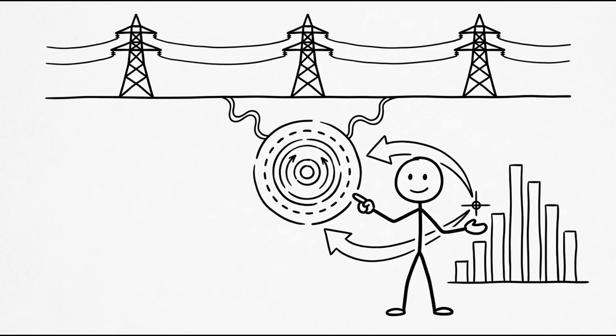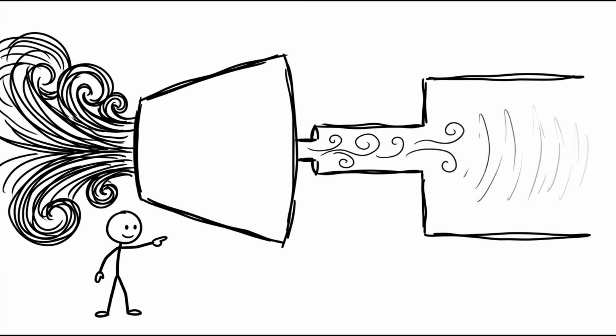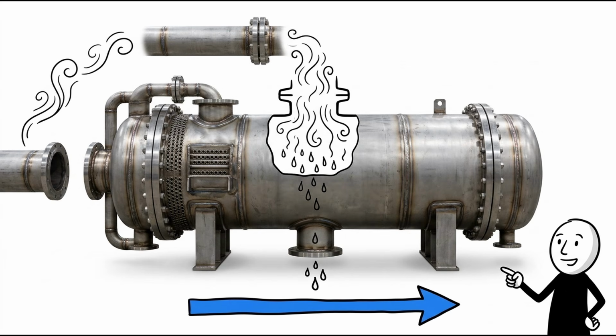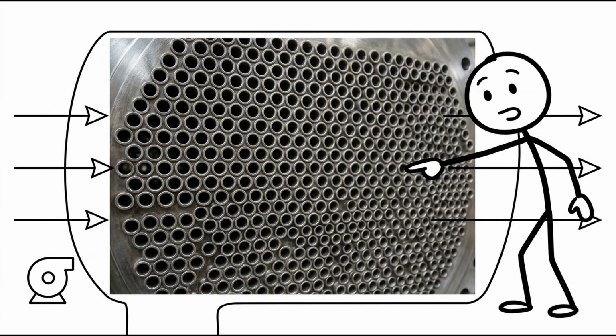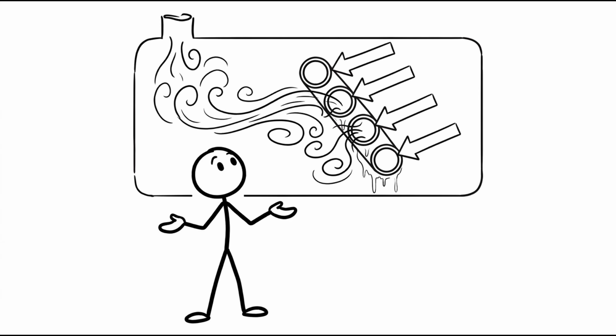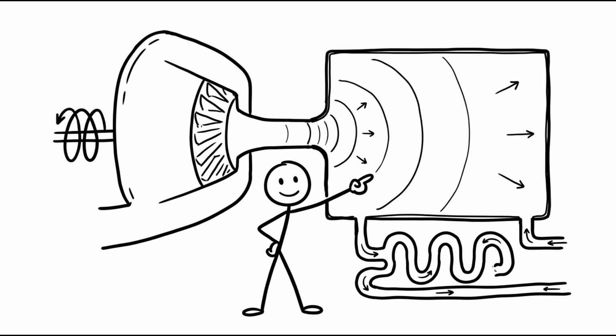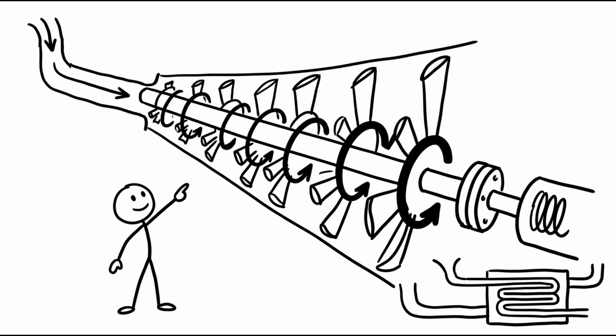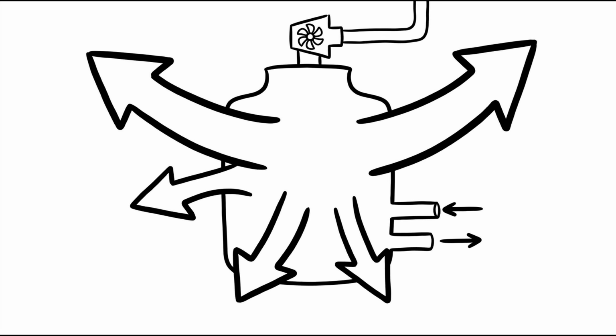to changes in demand. After passing through the turbine, the steam has released most of its useful energy. Instead of being thrown away, it enters a large condenser where it is converted back into liquid water. The condenser contains thousands of tubes carrying cooling water. When the exhausted steam comes into contact with the cold surfaces of these tubes, it loses heat and condenses. This creates a low-pressure environment at the turbine outlet, allowing the steam to expand more efficiently and extract additional energy from the turbine.